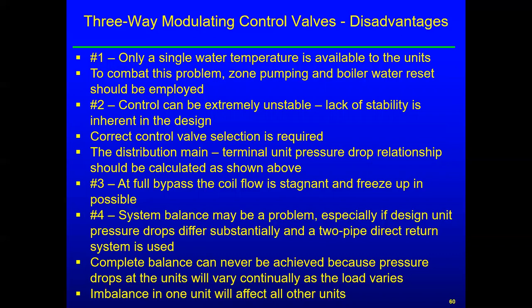Control can be unstable, and we talked about that based on those pressure drops. Getting the control valve selection with a significant pressure drop across that coil is important. The distribution main terminal unit pressure drop relationship should be calculated, as we talked about above. If we go to full bypass through the coil, or bypassing the coil is stagnant, and again we have freeze up potential. System balance can be a problem, and complete balance can never be achieved because pressure drops in the units vary continually as unit load varies, and imbalance in one unit will affect the other units. So there's issues.